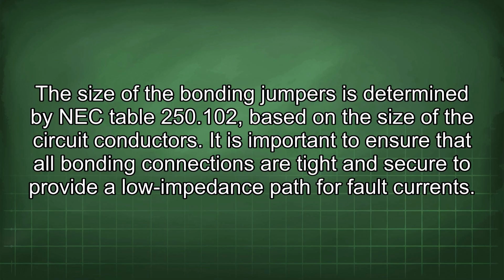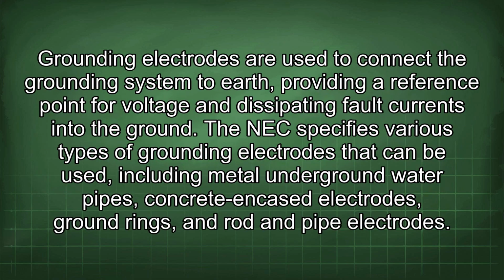It is important to ensure that all bonding connections are tight and secure to provide a low impedance path for fault currents. Grounding electrodes are used to connect the grounding system to the earth, providing a reference point for voltage and dissipating fault currents into the ground. The NEC specifies various types of grounding electrodes that can be used, including metal underground water pipes, concrete encased electrodes, ground rings, and rod and pipe electrodes.